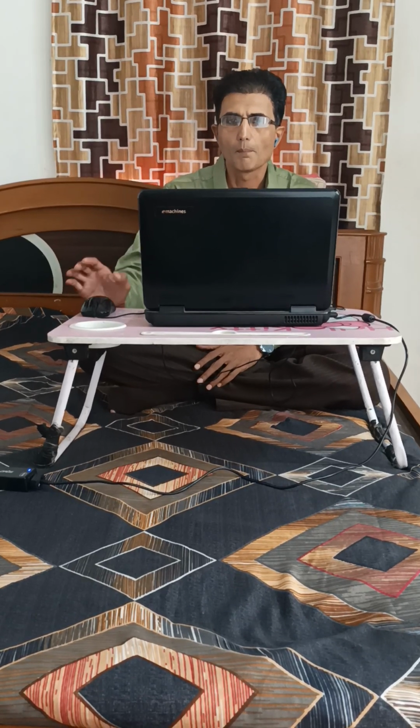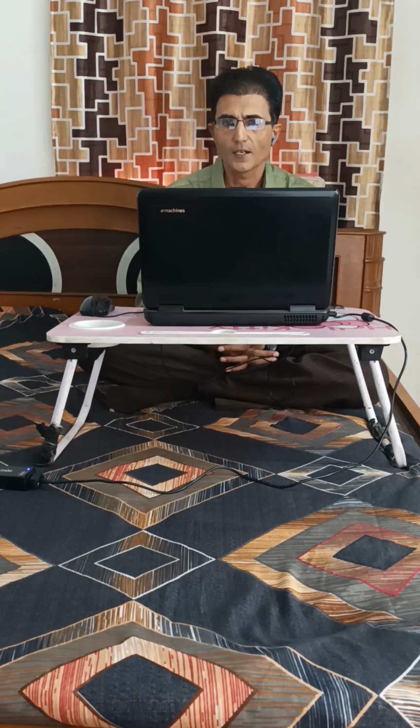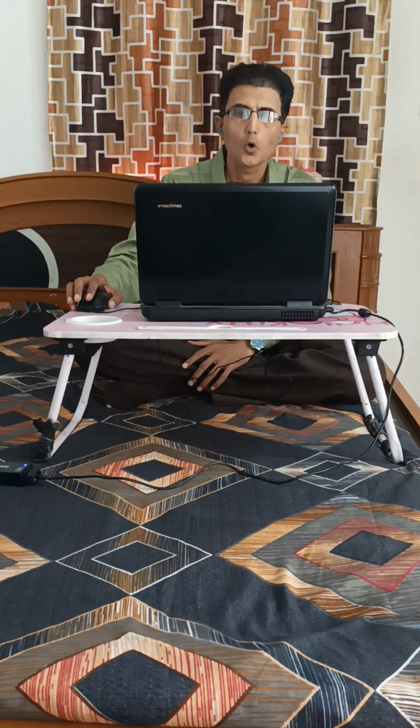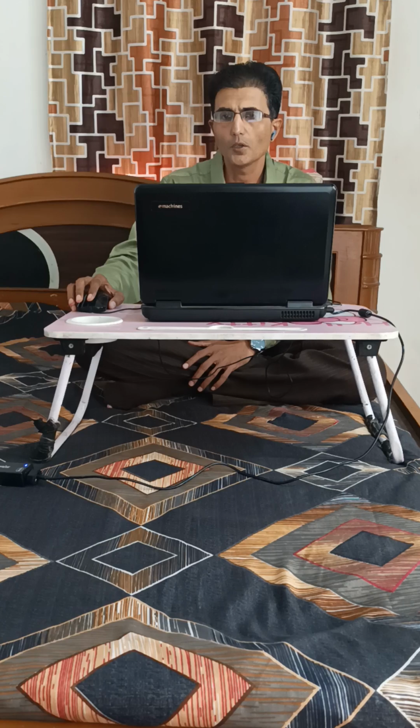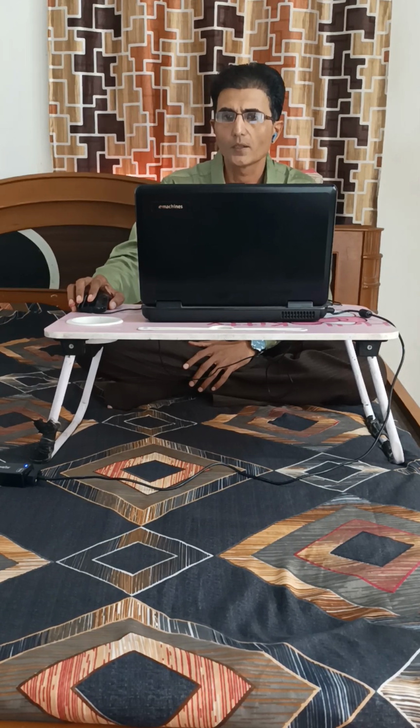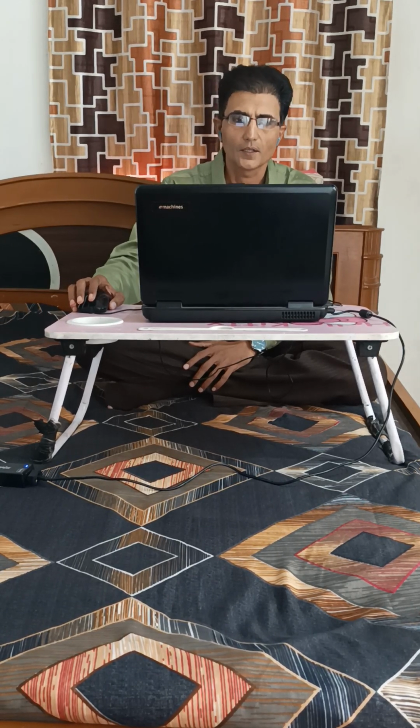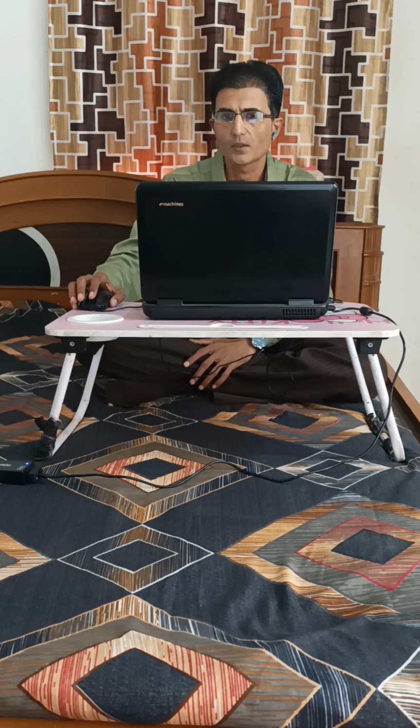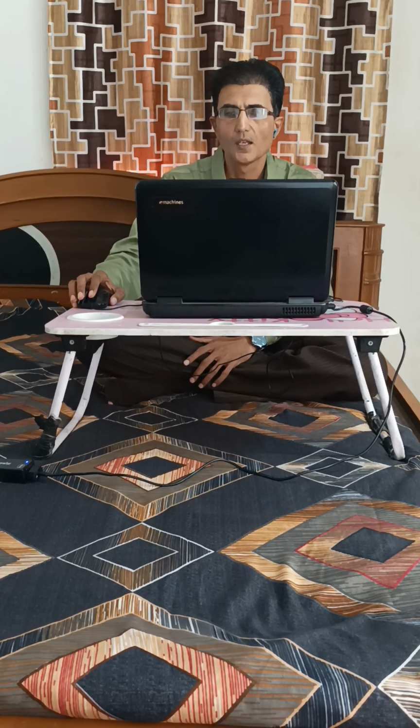Capillary columns are made of glass or fused silica. These columns are much longer, between 10 meters and 100 meters long, with a small internal diameter of 0.1 to 1 mm. The inner column is coated with a thin layer of stationary phase so the molecules can come into contact with the wall of the tubing.